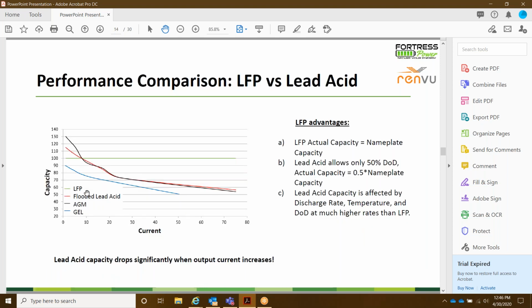I want to bring up this quick chart of a performance comparison between lithium iron phosphate and lead acid. This chart shows that with a higher influx of current, your capacity of lithium will stay the same at 100%. Now, with flooded lead acid, AGMs, or gel batteries, as your current goes up, your capacity is going to drop. What does this mean?